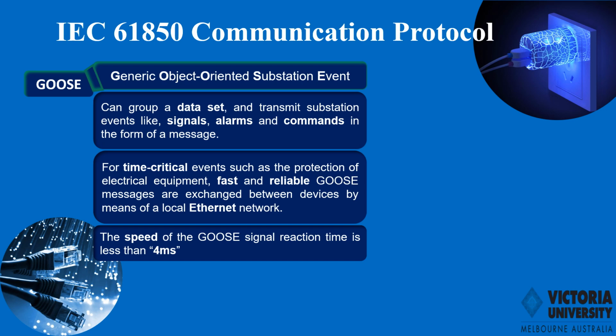One of the significant achievements of the IEC 61850 standard is the GOOSE protocol. Its GOOSE signal has specific details, namely the GOOSE ID, MAC address, virtual local area network priority, dataset, and data attributes. This makes it recognizable in the network. The GOOSE can group a data set and transmit substation events like signals, alarms, and commands in the form of a message. This is used for time-critical events, for protection of electrical equipment, and exchanging between devices by means of a local Ethernet network. And did you know that the GOOSE signal reaction time is less than 4 milliseconds?